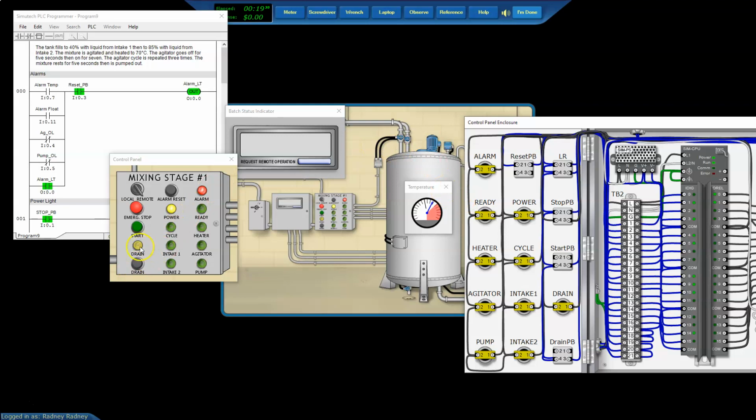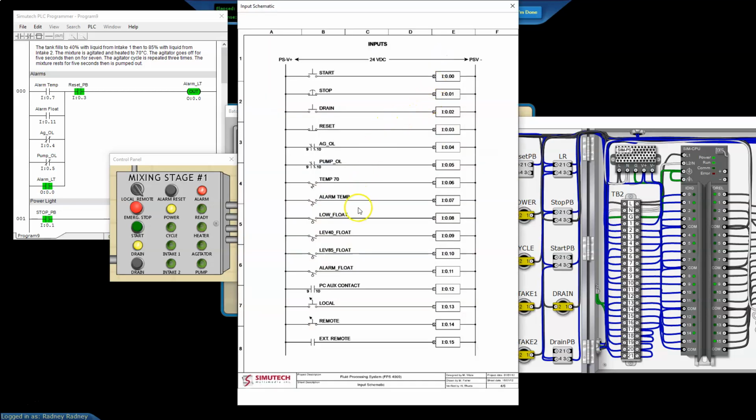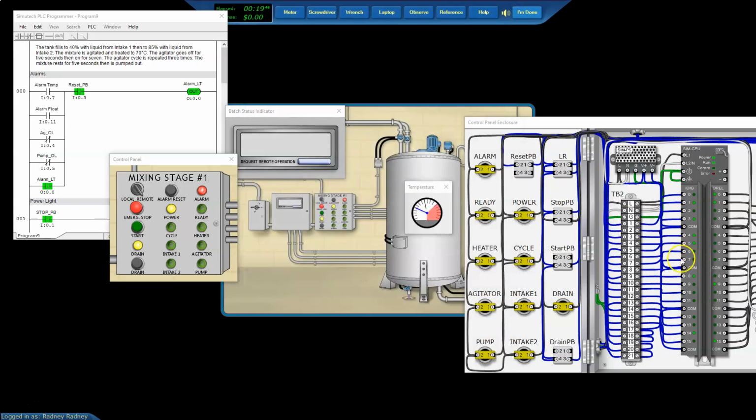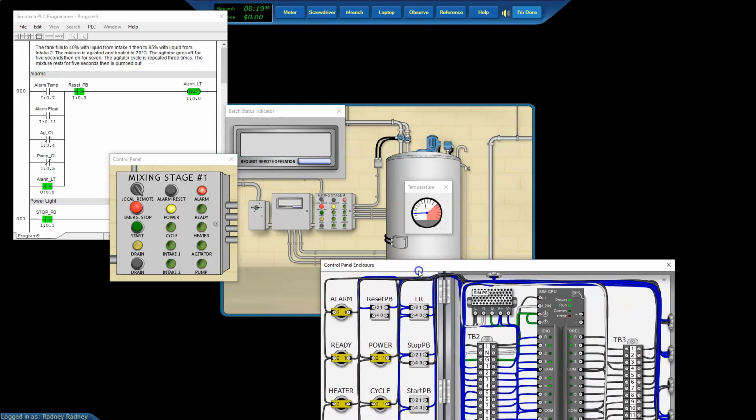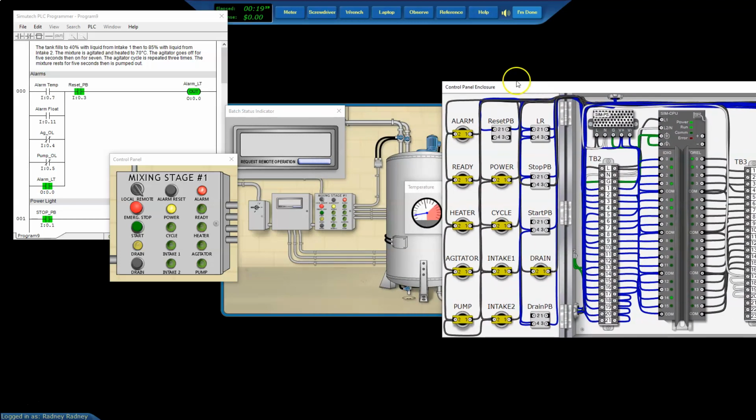So what we're going to do is drain our fluid. We're going to be looking at our reference one more time. And we know that 6 should come on. And if it does come on, we should never get to 7. It should cut us off once we hit 6. So we're going to see if we see 6 come on and then 7. But I think what we're going to find is only 6 comes on and not 7. I'm going to get it where you can see the temperature sensor too.